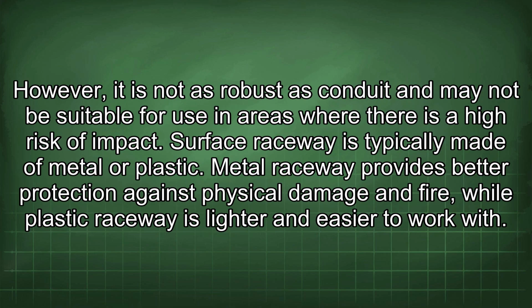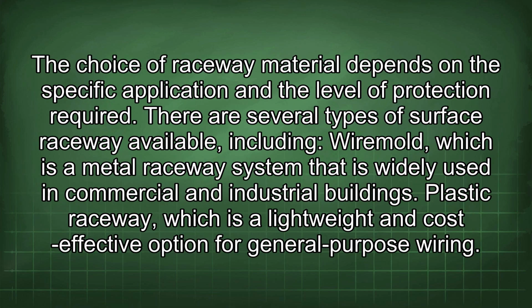However, it is not as robust as conduit and may not be suitable for use in areas where there is a high risk of impact. Surface raceway is typically made of metal or plastic. Metal raceway provides better protection against physical damage and fire, while plastic raceway is lighter and easier to work with. The choice of raceway material depends on the specific application and the level of protection required.